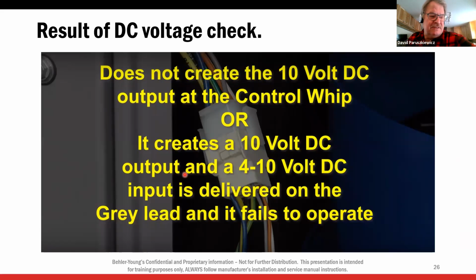So you might walk up onto this unit and the motor's not running, and I have my 10 volts DC. I don't have my 9 volts DC or whatever my return voltage is, and the motor's not running. Before you condemn that motor, shut the disconnect off for 3 minutes, all right? Patience. We gotta allow the capacitor to discharge, and then power it back up and see if the motor comes on. It may have locked itself out on over voltage.